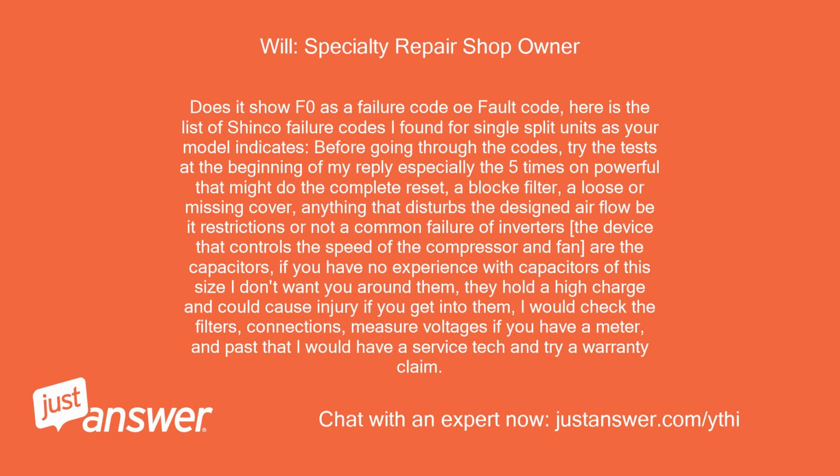A common failure of inverters, the device that controls the speed of the compressor and fan, is the capacitors. If you have no experience with capacitors of this size, I don't want you around them. They hold a high charge and could cause injury if you get into them. I would check the filters, connections, measure voltages if you have a meter, and past that I would have a service tech look at it and try a warranty claim.